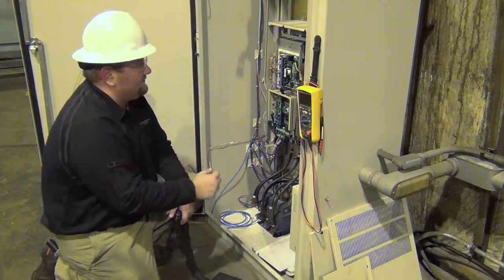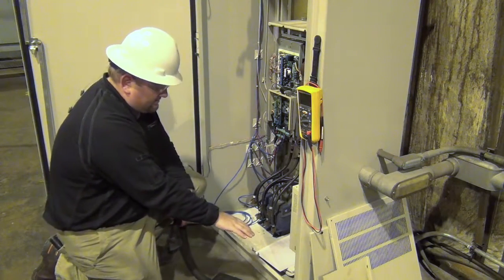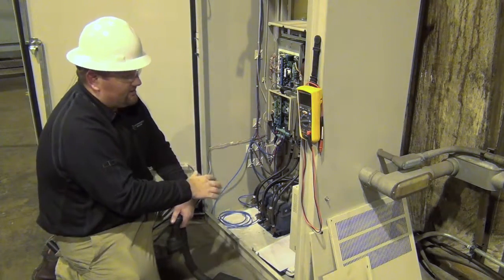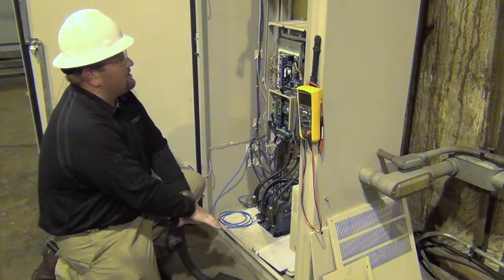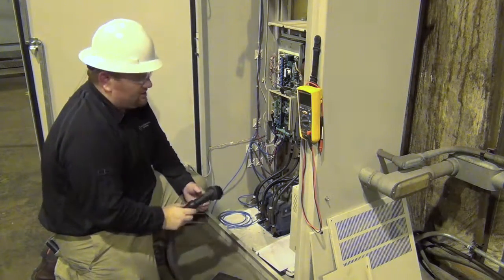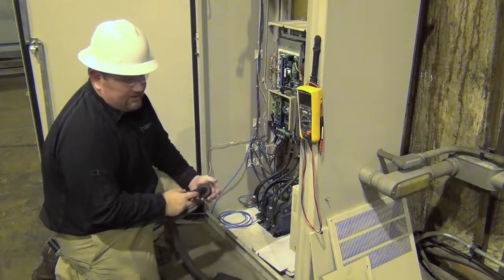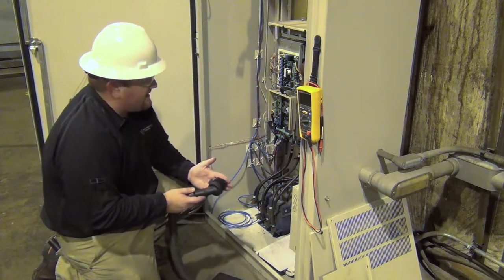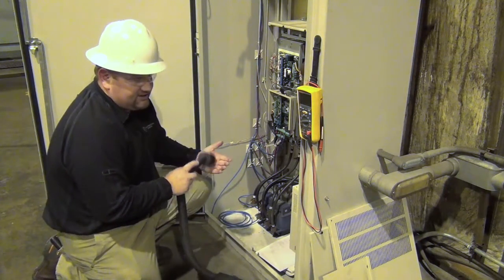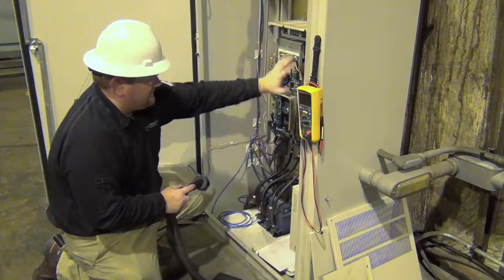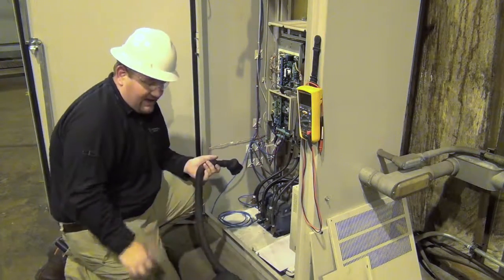So it's probably hard to see on the video, but you'll notice there's quite a bit more debris in the bottom of this cabinet now that I've flushed quite a bit of it back. So now what we're going to do is actually work our way backwards up the drive with the vacuum cleaner and pick out anything that we can see. Again, this is an ESD safe vacuum cleaner, specifically made for whenever we're going to vacuum anything that's inside of the drive or a braking package.